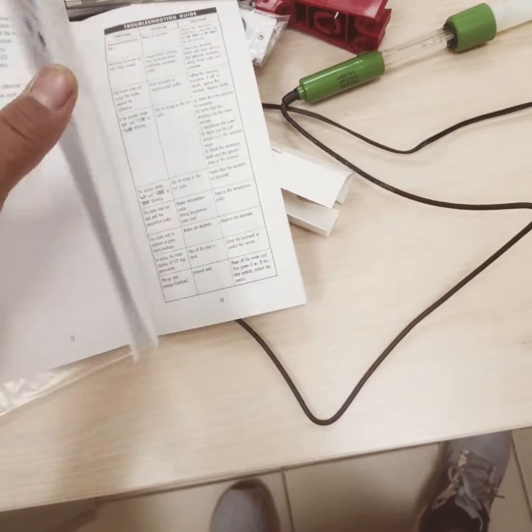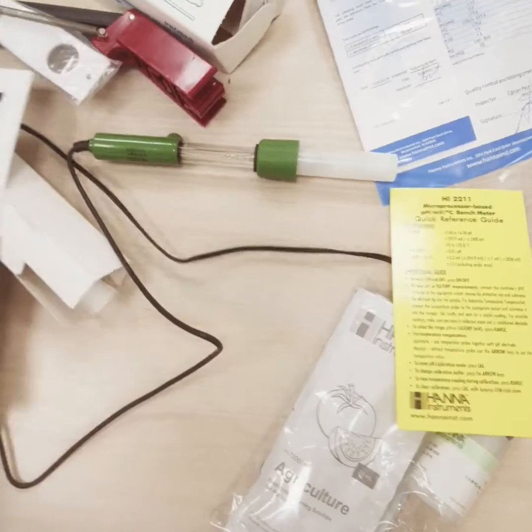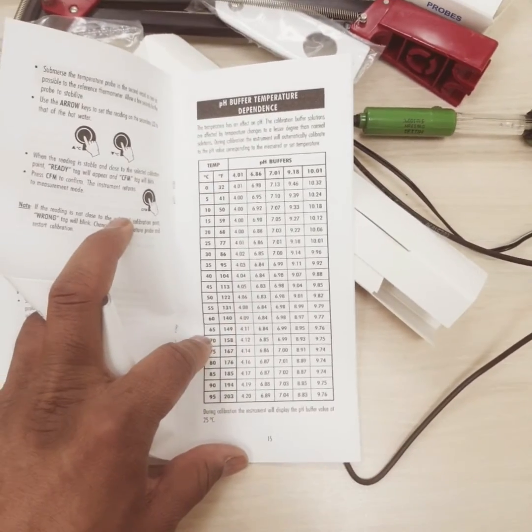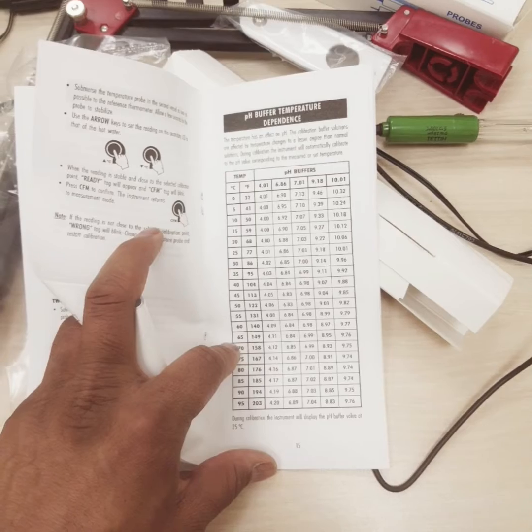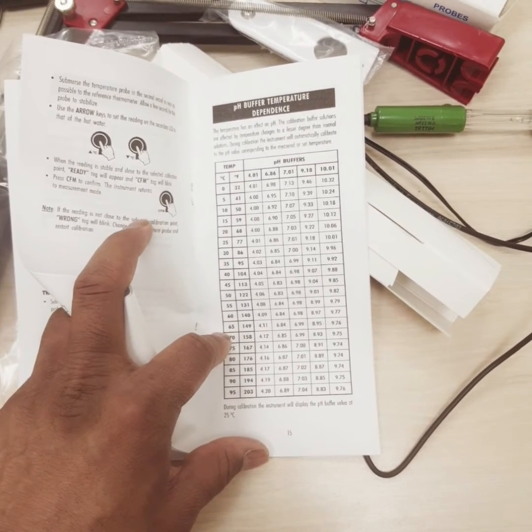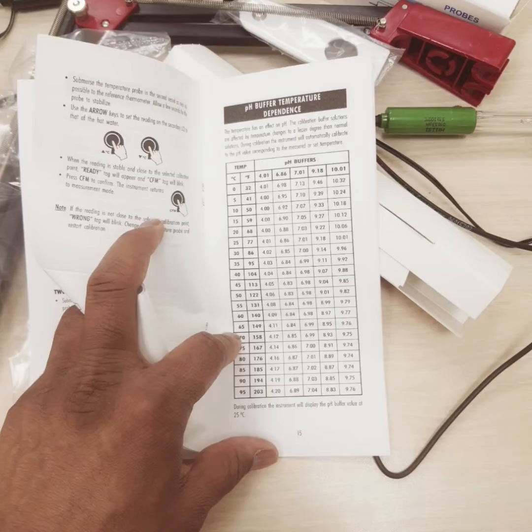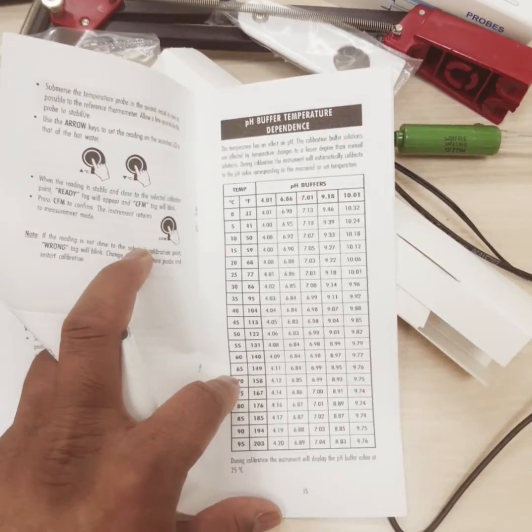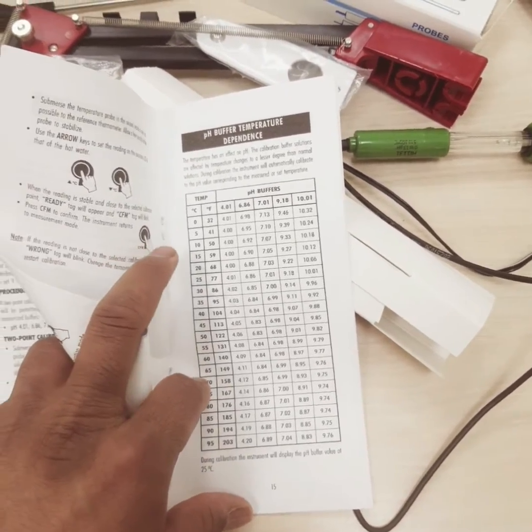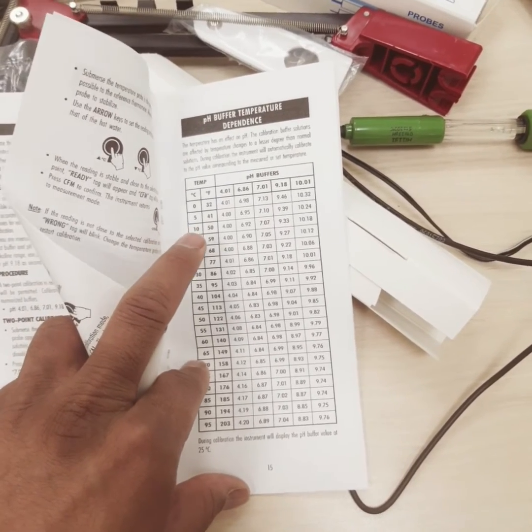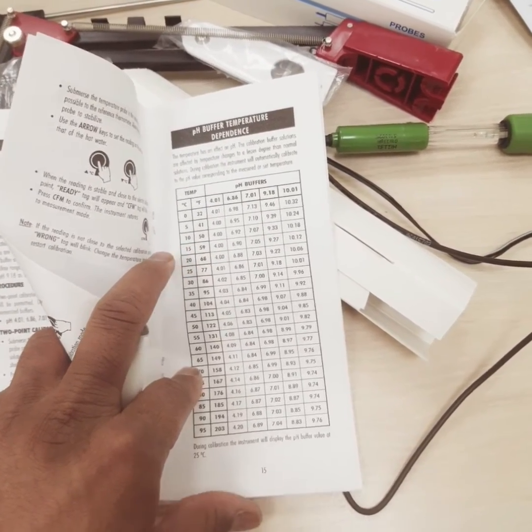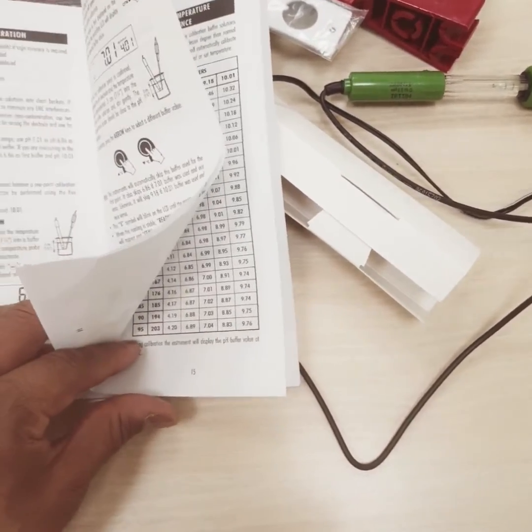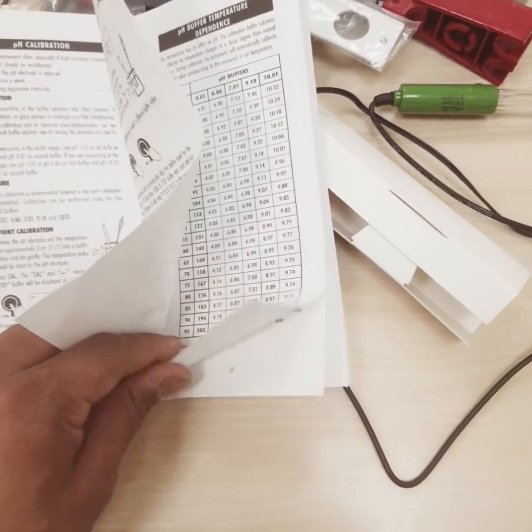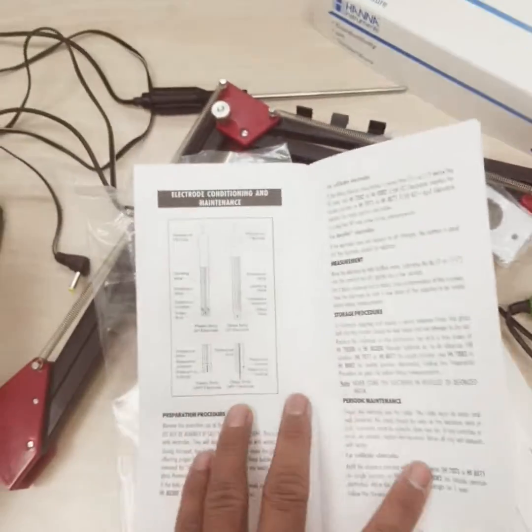And then here in the manual we have some very important things that usually I don't find in a lot of videos. So here you can see the pH temperature dependence, usually at 0 degrees C or 32 degrees Fahrenheit. So you can see 4 will read 4, and 6.86 will read 6.98, and 7 will read 7.13. Similarly, if you are increasing the temperature, you can see there is a variation in the reading of the pH. So pH and temperature are dependent. It says during calibration the instrument will display the pH buffer value at 25 degrees C.